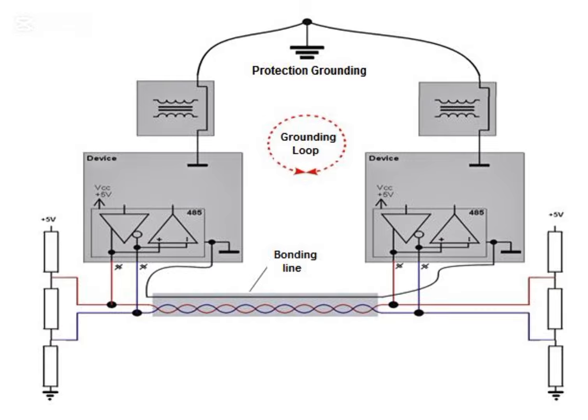Separate earth and ground. Avoid mixing power earth with instrument ground to prevent noise. Shield grounding for analog signals: ground the shield at one end, usually the control system side. Low impedance path: ensure earthing resistance is 1 ohm or less for safety. Surge protection: use lightning arresters and surge suppressors in the grounding system.